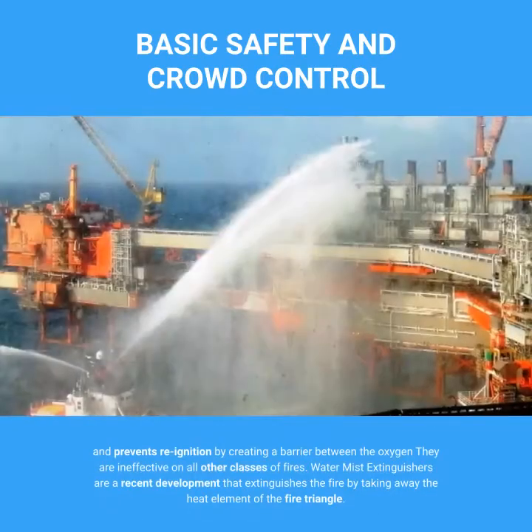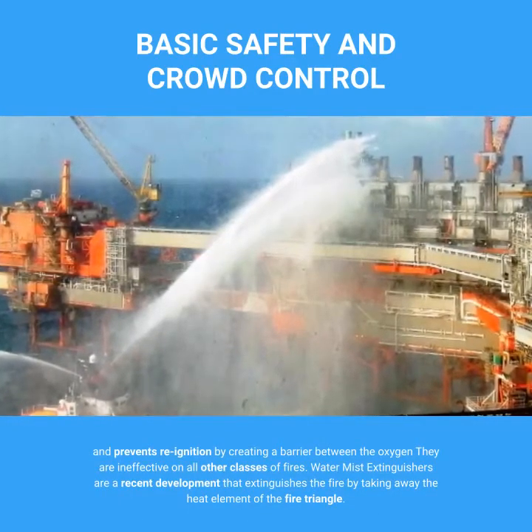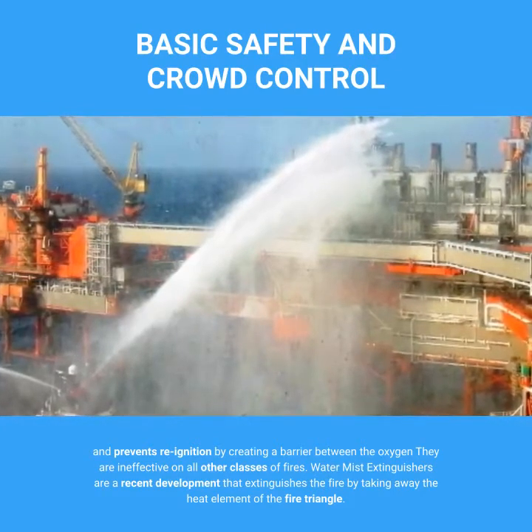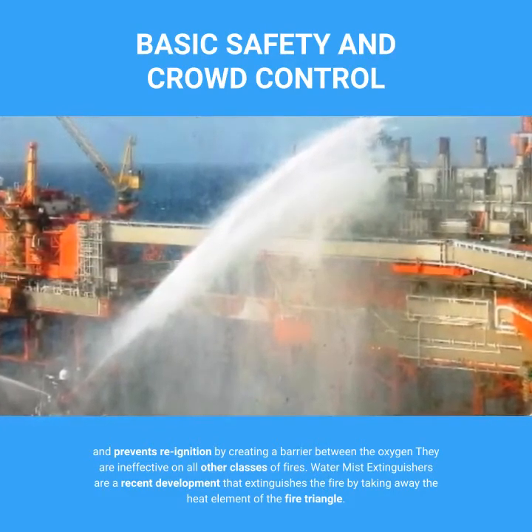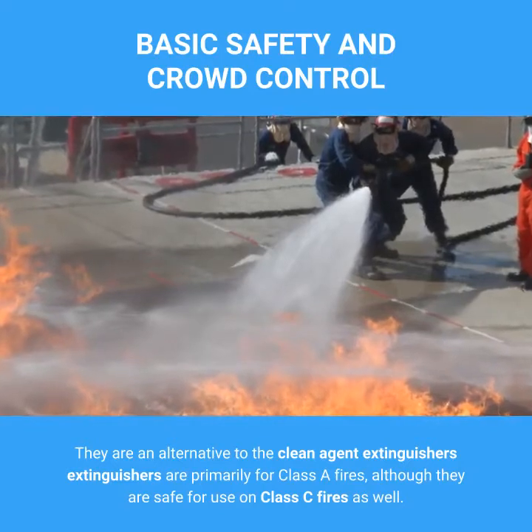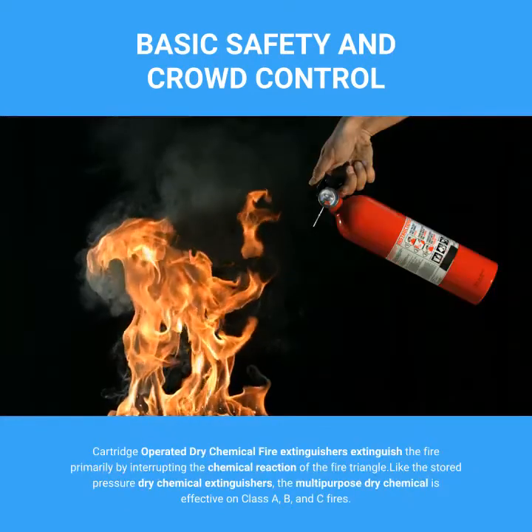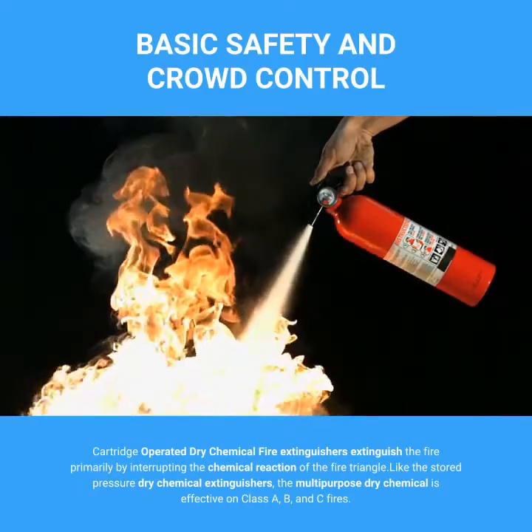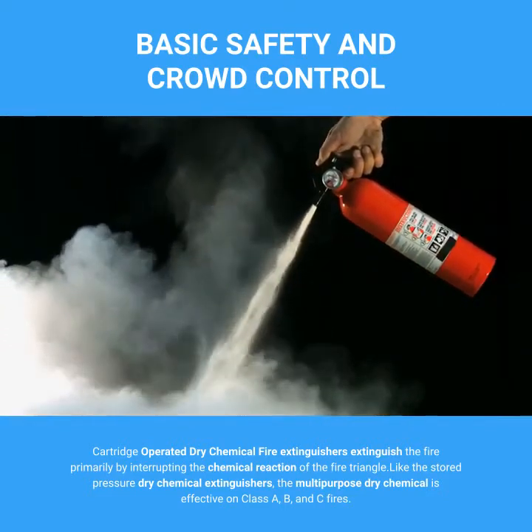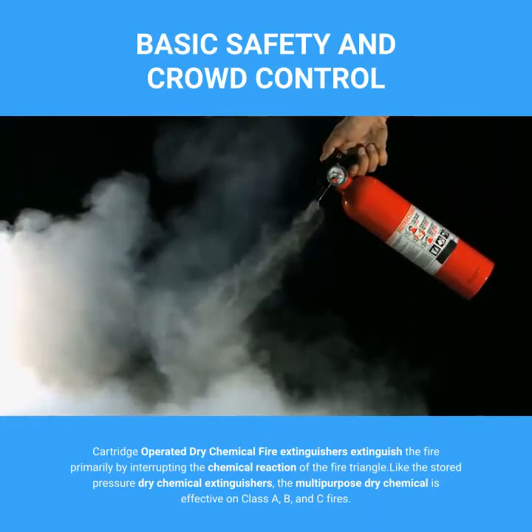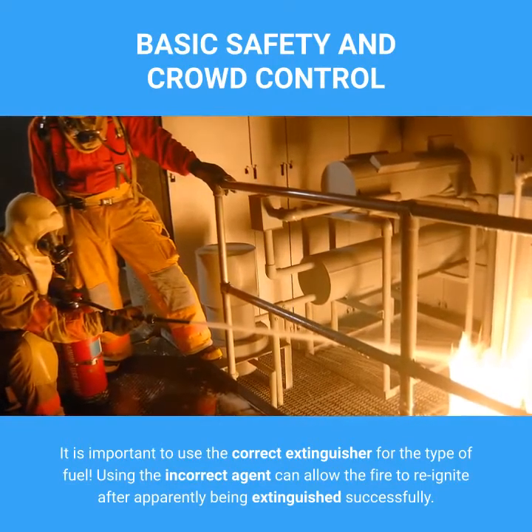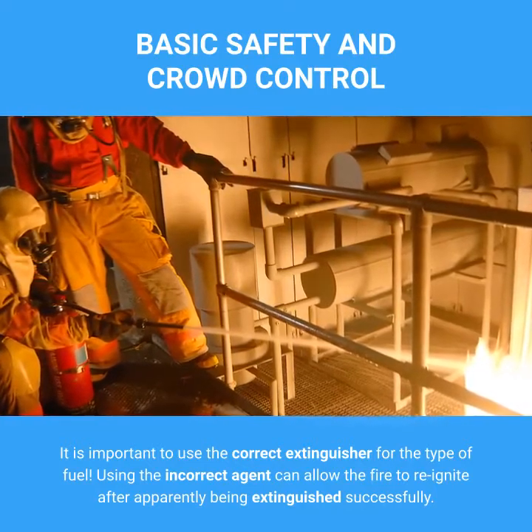Wet chemical is a new agent that prevents re-ignition by creating a barrier between the oxygen; it is ineffective on all other classes of fires. Water mist extinguishers extinguish fire by taking away the heat element and are an alternative to clean agent extinguishers, primarily for Class A fires but safe for use on Class C fires as well. Cartridge operated dry chemical extinguishers extinguish fire primarily by interrupting the chemical chain reaction; the multi-purpose dry chemical is effective on Class A, B, and C fires. It is important to use the correct extinguisher for the type of fuel, as using the incorrect agent can allow the fire to reignite after apparently being extinguished successfully.